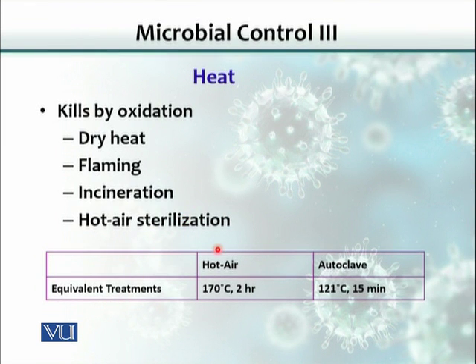Comparing temperatures required for sterilization: these methods achieve complete removal. For hot air sterilization, the temperature must reach 170 degrees Celsius, and the object must remain at that temperature for at least two hours. With moist heat, the equivalent temperature is 121 degrees Celsius, and it requires only 15 minutes.